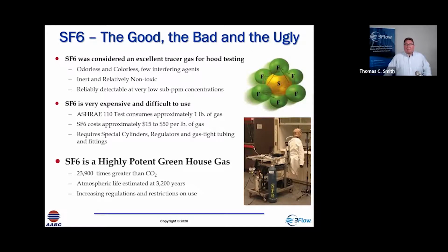And as a result, it's being banned and discouraged in facilities all over the United States and all over the world. So ASHRAE sponsored a research project to come up with an alternative. And so we're working on that right now. The typical ASHRAE test, the sulfur hexafluoride, can cost you somewhere between $15 to as much as $50 per pound of gas. And it takes about a pound of gas to do a single ASHRAE 110 test.